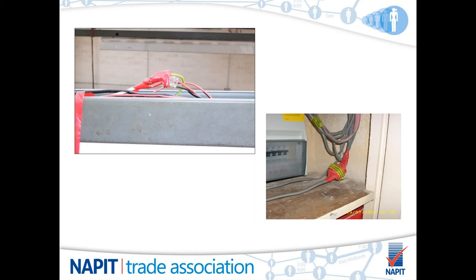These pictures show cables that have been either extended or repaired with the use of connector blocks. Now, the top picture shows an exposed conductive part with metallic trunking, which would be listed as a code 1 because there is direct contact to the terminals. The below picture shows the use of connector blocks wrapped in insulation tape. Whilst this is not the preferred method to join a cable, because there is no direct contact to the terminals, you would list this as a code 2.